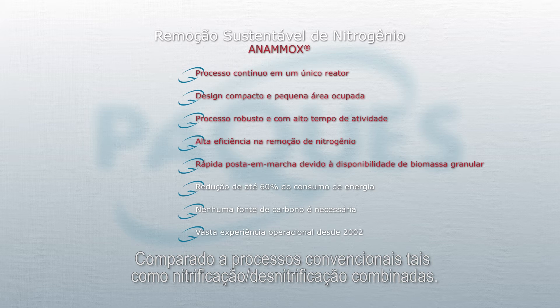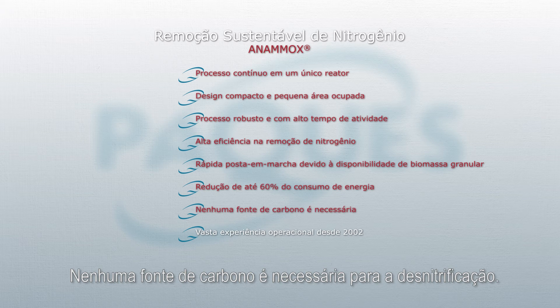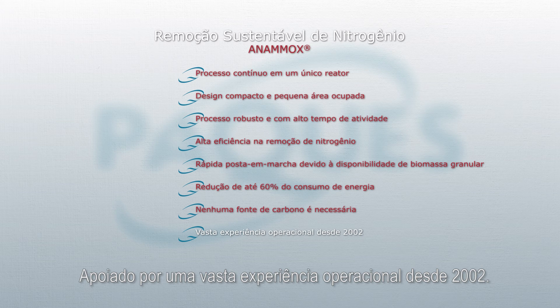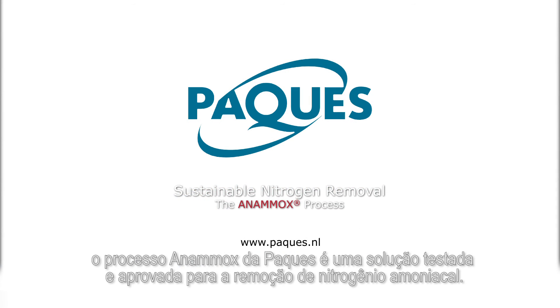Compared to conventional processes such as combined nitrification and denitrification, the Paques Anammox process has the lowest cost of ownership, with a 60% saving on energy consumption and CO2 emissions. No carbon source is needed for denitrification. Backed up with extensive full-scale operational experience since 2002, the Paques Anammox process is the proven and tested solution for the removal of ammonium.